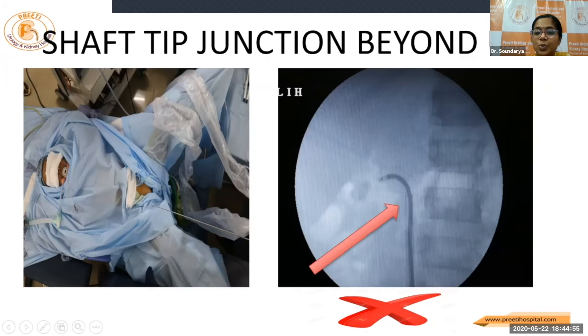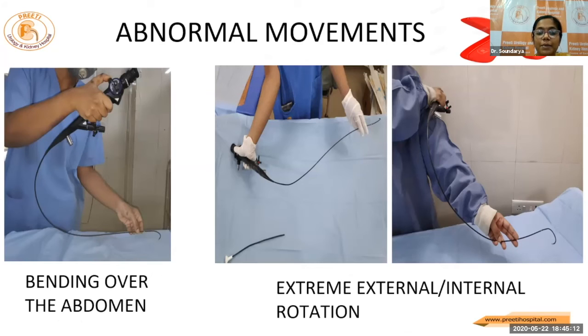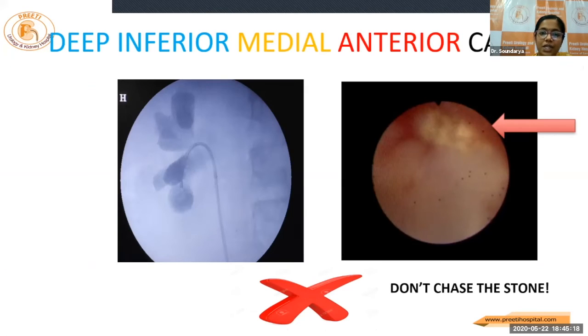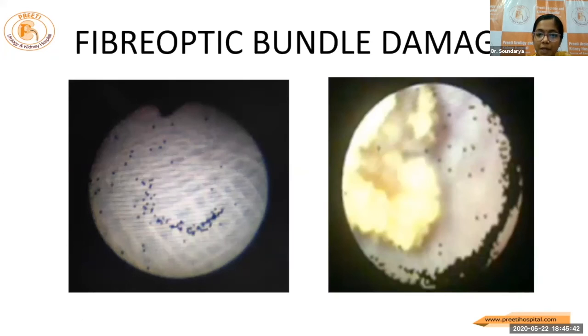We have seen the stone — that doesn't mean we can start bending right away. Avoid abnormal movements like extreme external or internal rotation, especially if the scope lever is deflected. Avoid bending over the abdomen in enthusiasm to reach the lower calyx. Don't do such awkward movements. If the stone is seen at a difficult point and we have done maximum deflection but still cannot reach it — don't chase the stone, especially deep medial, inferior-most, and anterior calyces. Likewise, the upper calyx can also trouble you. With more extreme torque, it may cause breakage of the scope or fiber optic bundle damage. Once some bundles are damaged, the threshold is lowered and other bundles will be quickly damaged.